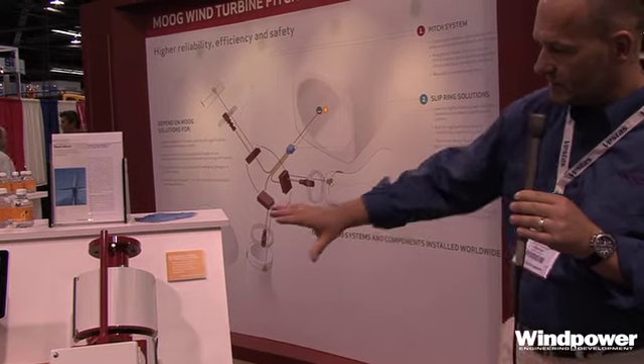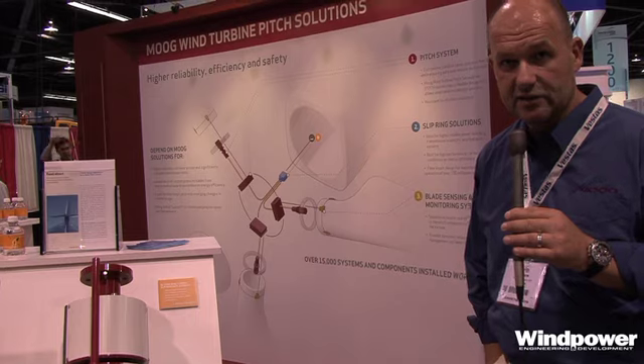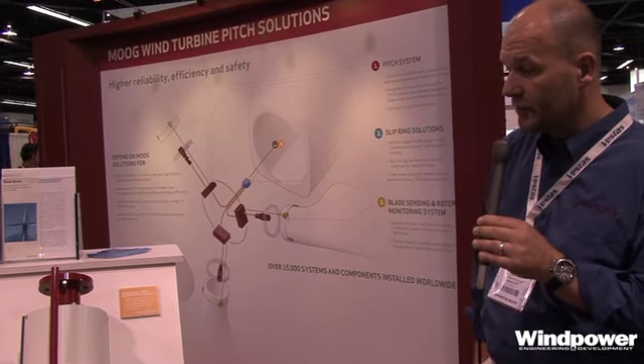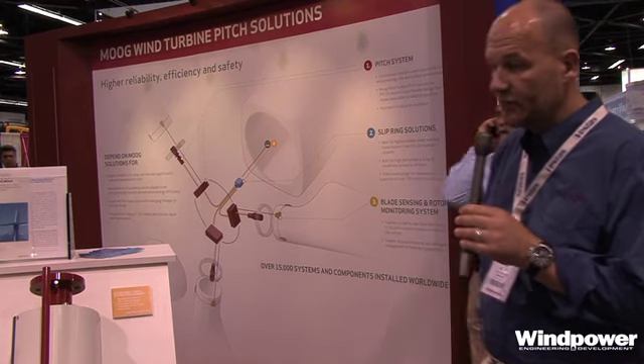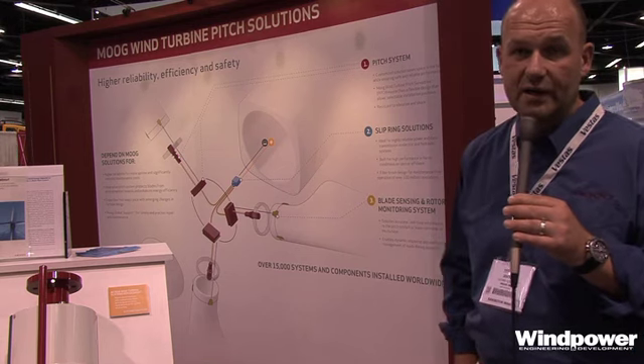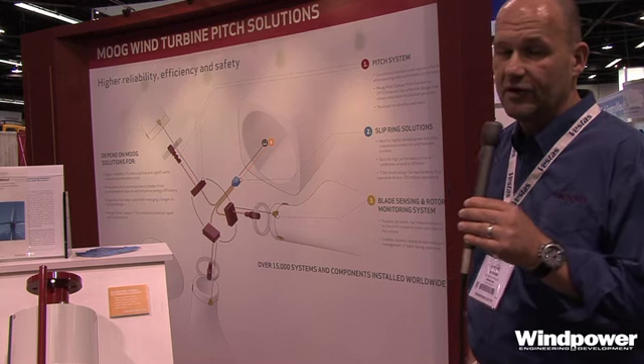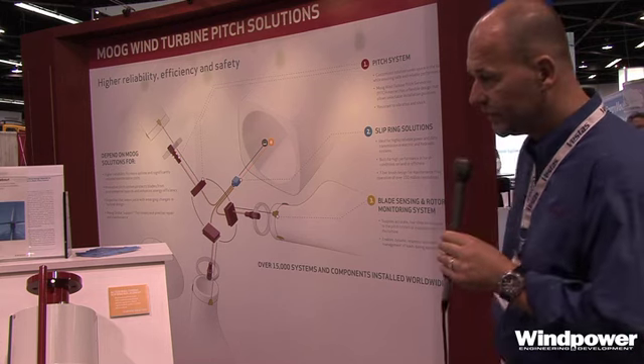in that special device we are using for replacement in the aftermarket for one of the big wind turbine manufacturers, for a 1.5 megawatt turbine. Such slip rings have a very high reliability, they are maintenance free, and they survive for more than 100 million revolutions. 100 million revolutions is a very good part of the wind turbine life, probably the whole life.